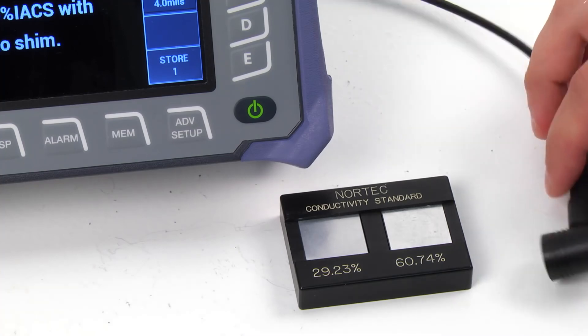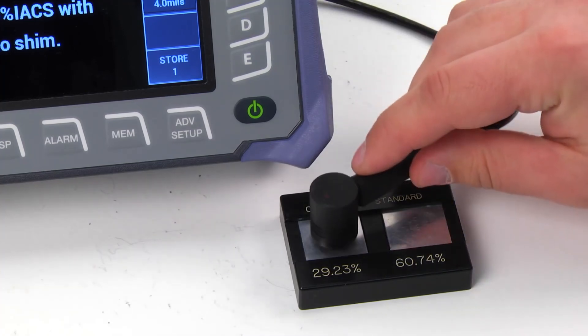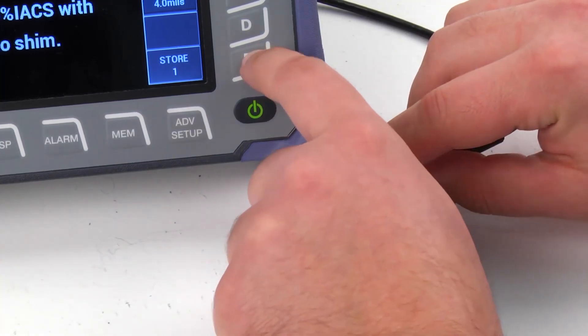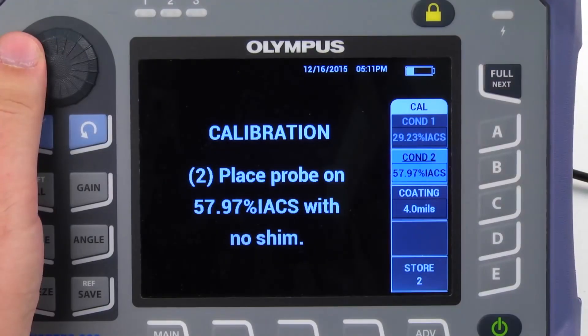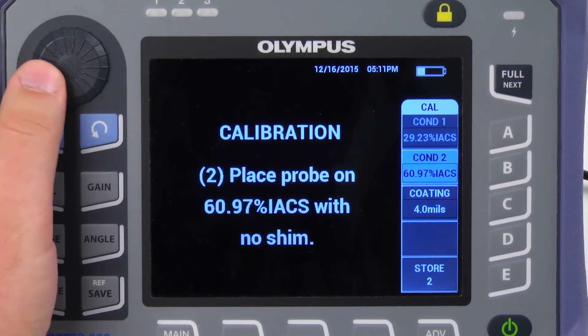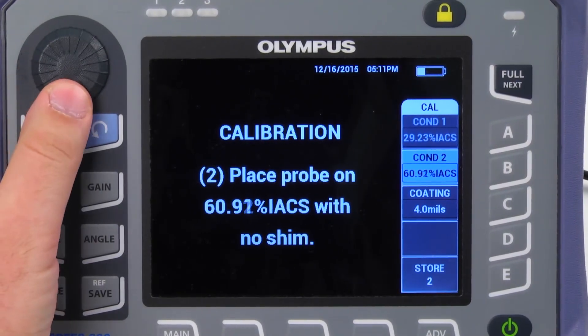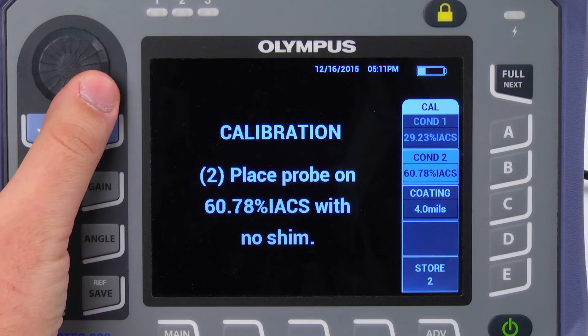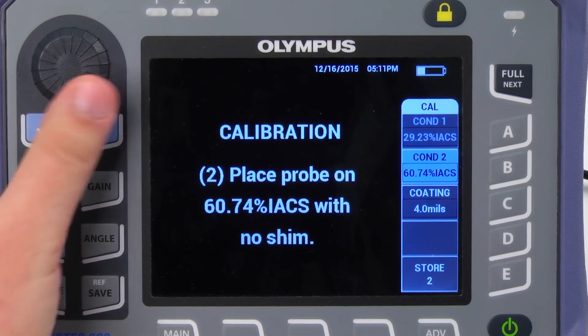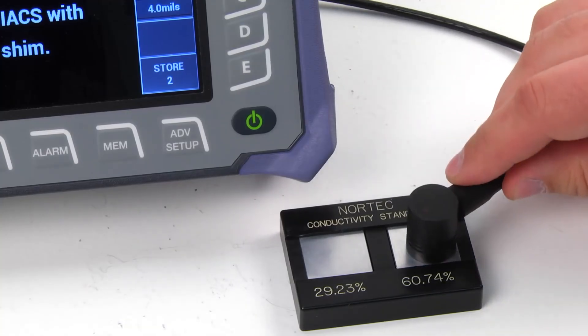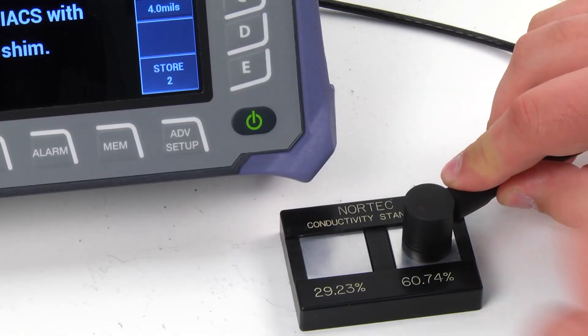Place the probe on the standard and press E to store the reading. Next, enter the value for the right-hand side standard. Place the probe on the standard and press E to store the reading.